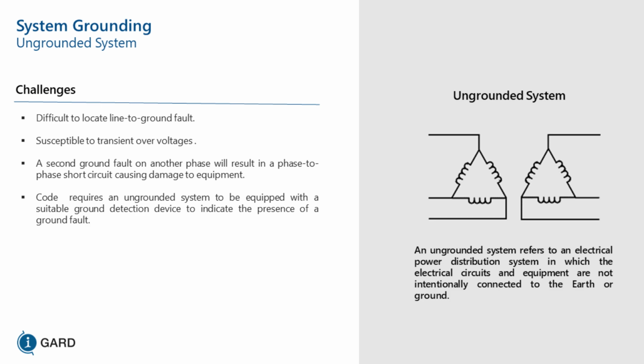You have no current, and the only thing you're going to see if you measure phase to ground is, if you have a 480 volt system, when the system is healthy, you're going to measure 277 volts to ground on each phase. If you have a ground fault, you're measuring 480 volts phase to ground on the two ungrounded phases and 0 volts to ground on the faulted phase. And unfortunately, the voltage applies to that phase conductor throughout your entire facility, so you can't find the ground fault.